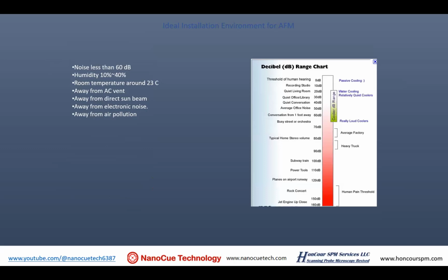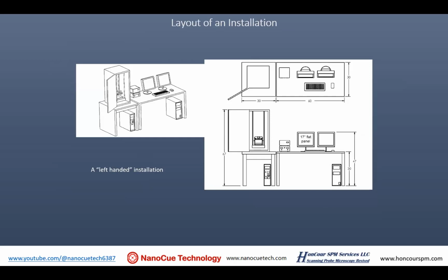This is a table that describes how you estimate your noise level. For example, here a typical home stereo volume is 80 dB, and a recording studio is 10 dB, which is very quiet, and so on and so forth. It helps you estimate your noise level in a typical situation. In AFM, you try to install a system in the quietest place possible, because the noise will kick into your imaging itself. This is a typical installation site of an Agilent Technologies AFM.